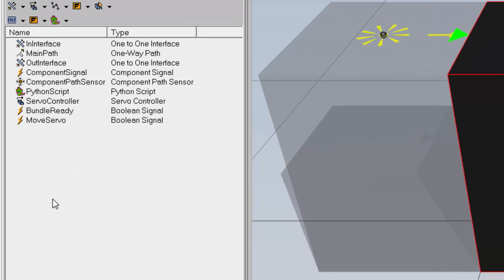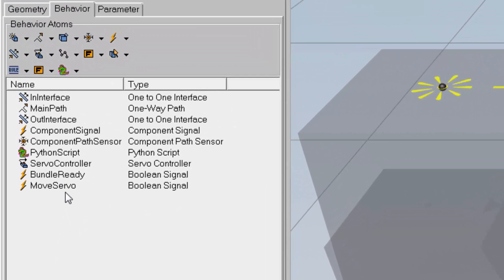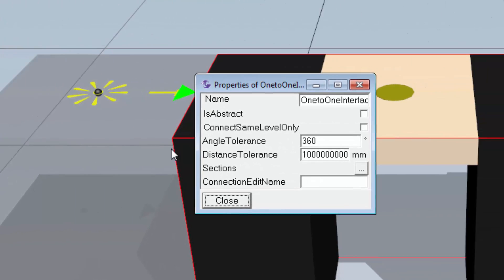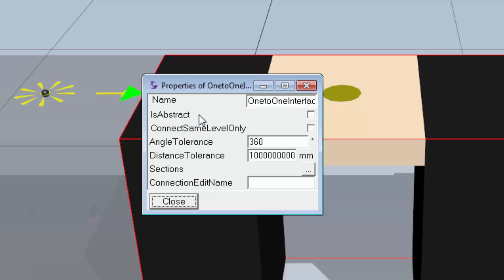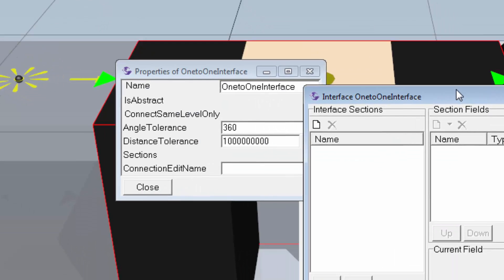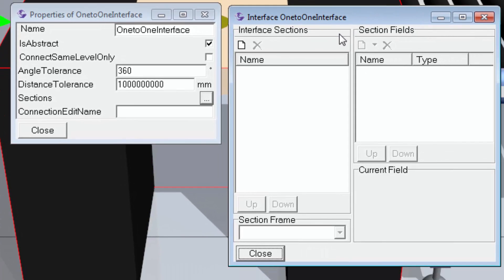Now to connect these two signals to the PLC connection, I need to create an interface. I'll go to the drop-down menu for interfaces and click One-to-One Interface. The first thing to set up is that the interface is abstract — I'll select the abstract checkbox — which means I'm forming a remote connection, not a physical one. I then need to create a section in this interface. In the sections property, it's very important to create a section named 'PLC' — capital P, capital L, capital C.